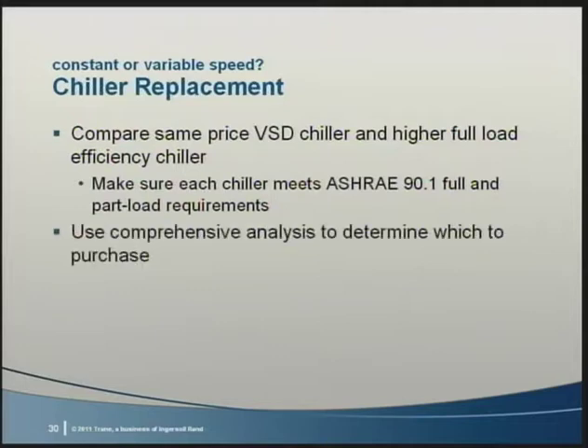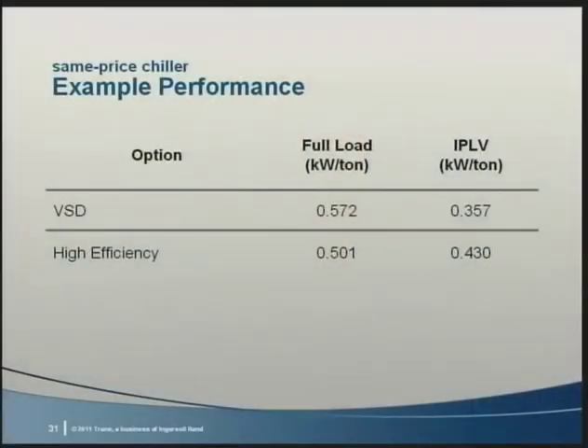Then use a fully featured analysis tool to determine which has a better return on investment. After all, there are ongoing differences in maintenance costs between fixed and variable speed chillers. Here's an example performance for some equal price chillers, one with and the other without a variable speed drive. The fixed speed chiller has better full load performance, but its IPLV is not quite as good. So which would most benefit a building owner? Let's look at an example, then give some general guidance.